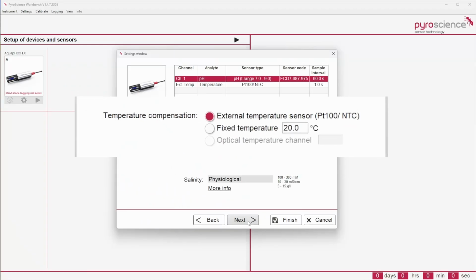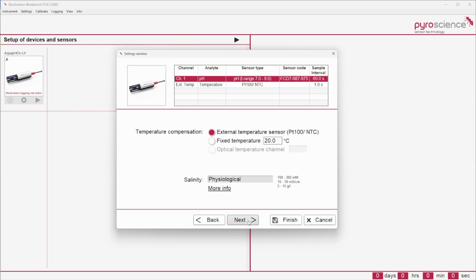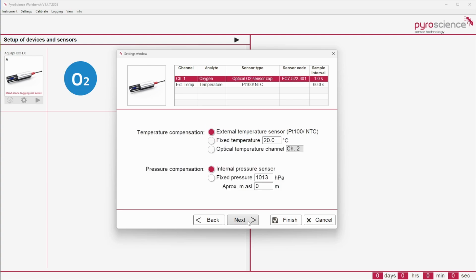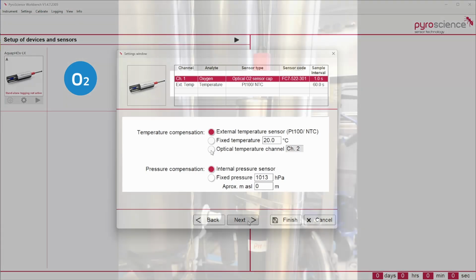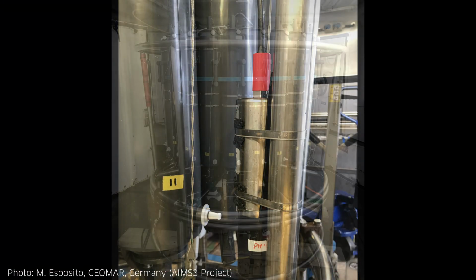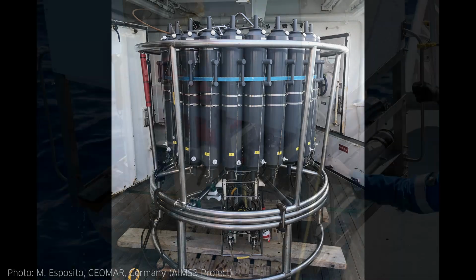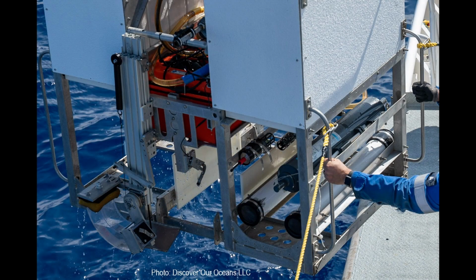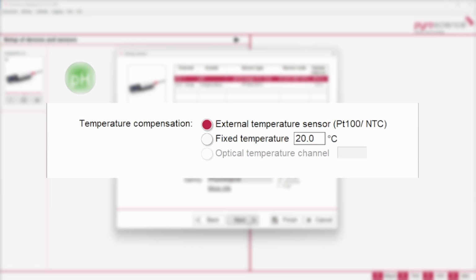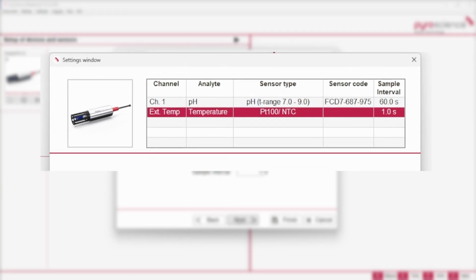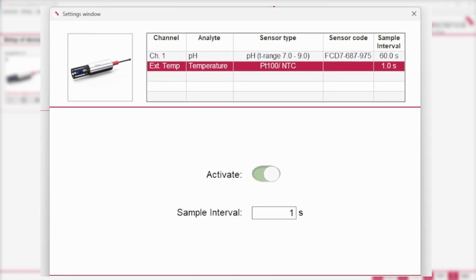The last adjustment is the temperature compensation. This setting is important for correct measurements. The temperature compensation can be provided by using an external temperature sensor. It is always recommended to use the external temperature sensor. For some oxygen units, it might be possible to select a pressure compensation. However, the recorded data do not show the environmental pressure, and therefore it is essential to use a third-party hydrostatic pressure sensor simultaneously with the AquapHOx measuring device for pressure compensation purposes, as there is no correct pressure measured by the device. For pH sensors, you will have to choose the temperature compensation and the salinity in this panel. In the last panel, the general settings of the external temperature sensors are shown. Ensure the sensor is activated and click on Finish.